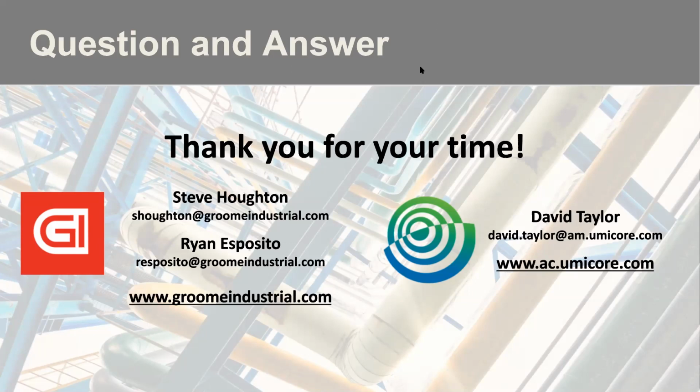Yep. From our side on a HRSG, we want to see permanent test grids on every new HRSG there is. I think it's going to save you a lot of trouble down the road. On smaller units, it might be easier to stick a probe in there and find out what you need. Yeah, another thing, Dave, that I'd like to discuss is your use of grid. Are you referring to a permanent sampling grid or the module frame assembly itself? There's a few things that we'd like to review with you there specifically.